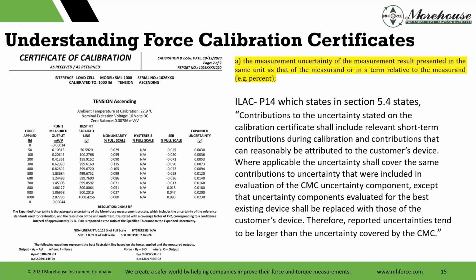And then we get into another thing. Talking about uncertainty, we need to state the measurement uncertainty of measurement results in the same unit as the measurand or relative to the measurand. So here's a certificate we have, a load cell that's in tension. And we're reporting the measurement uncertainty, and we're doing this per ILAC P14 as we need to abide by ILAC P14 as part of our accreditation. And ILAC P14 section 5.4 states, contributions to the uncertainty stated on the calibration certificate shall include the relevant short-term contributions during the calibration and contributions that can reasonably be attributed to the customer's device. Can reasonably be attributed. So what do you think that means?